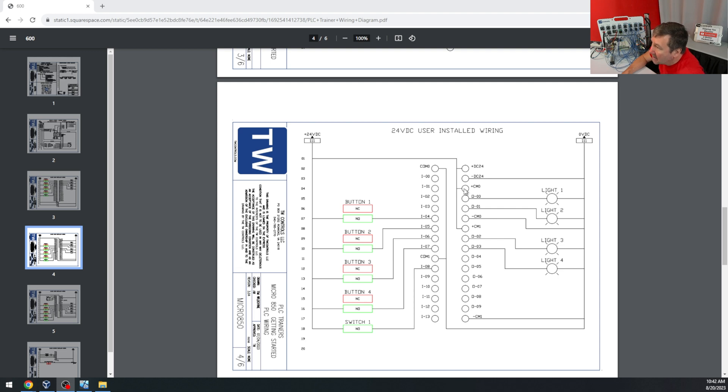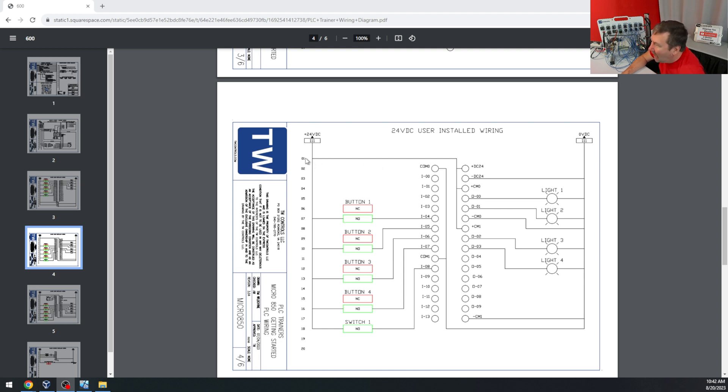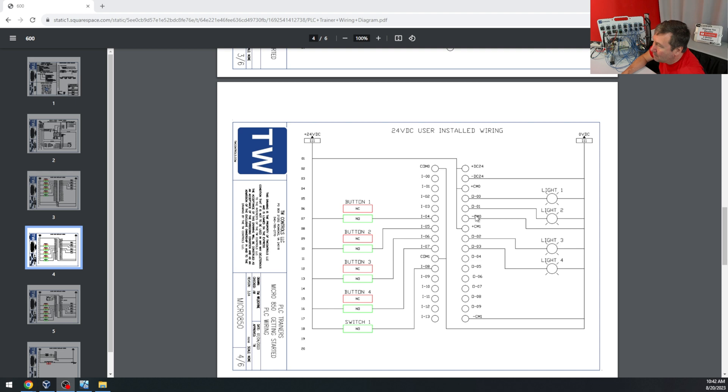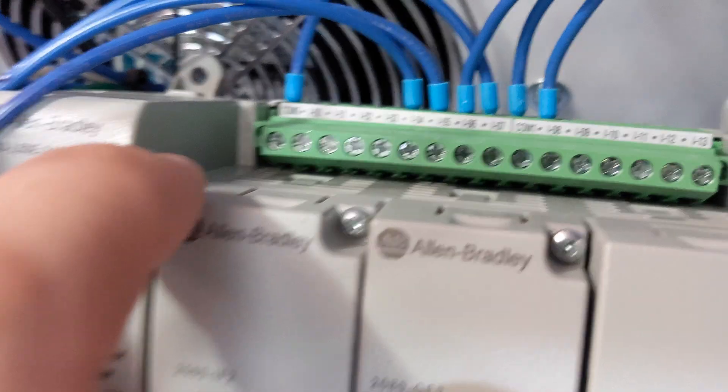Then we need to connect the plus CM0 and plus CM1 to the plus 24 volt DC. And usually people don't have problems with that because these are sourcing outputs. What I see people leave off is this minus CM0 and minus CM1. Those need to go to the minus of your power supply.